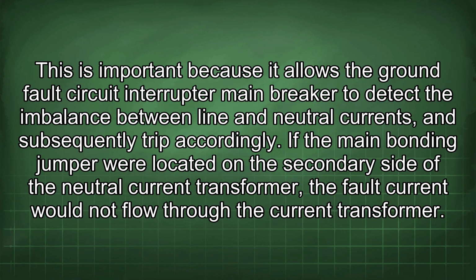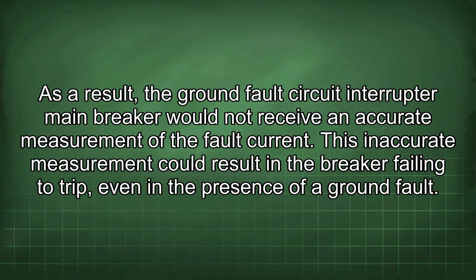If the main bonding jumper were located on the secondary side of the neutral current transformer, the fault current would not flow through the current transformer. As a result, the ground fault circuit interrupter main breaker would not receive an accurate measurement of the fault current. This inaccurate measurement could result in the breaker failing to trip, even in the presence of a ground fault.